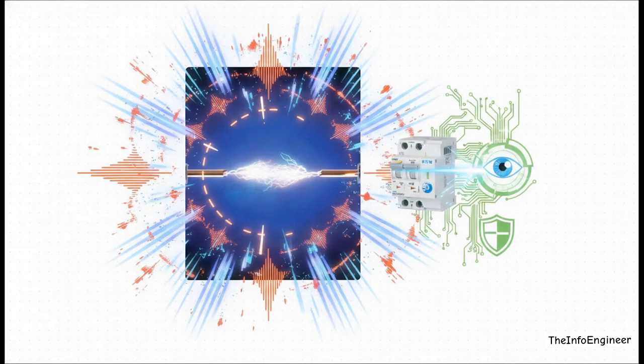So, a tiny loose connection can cause a very dangerous electrical arc. The problem is, conventional breakers will completely miss the characteristic high-frequency patterns of these faults, but modern devices like the Eaton AFDD Plus use highly sensitive electronics to actively monitor the installation. They identify and shut down these hidden dangerous sparks long before they can start a fire.